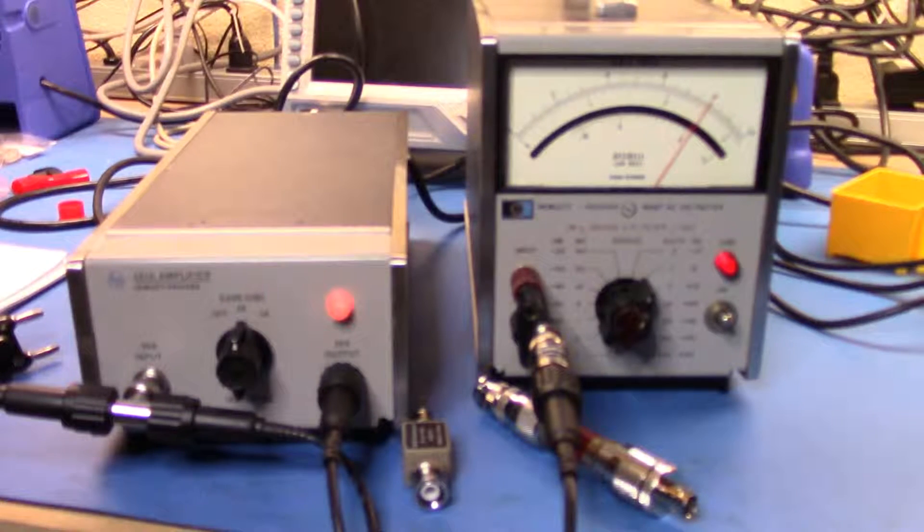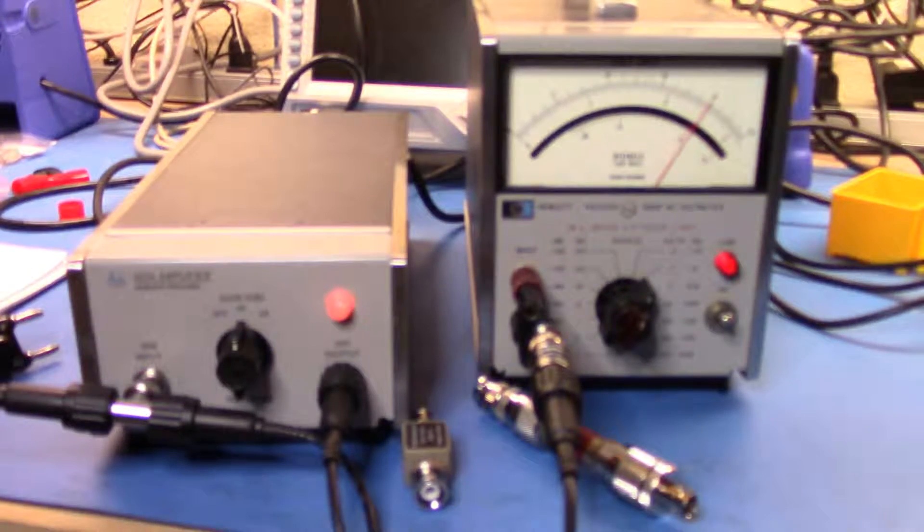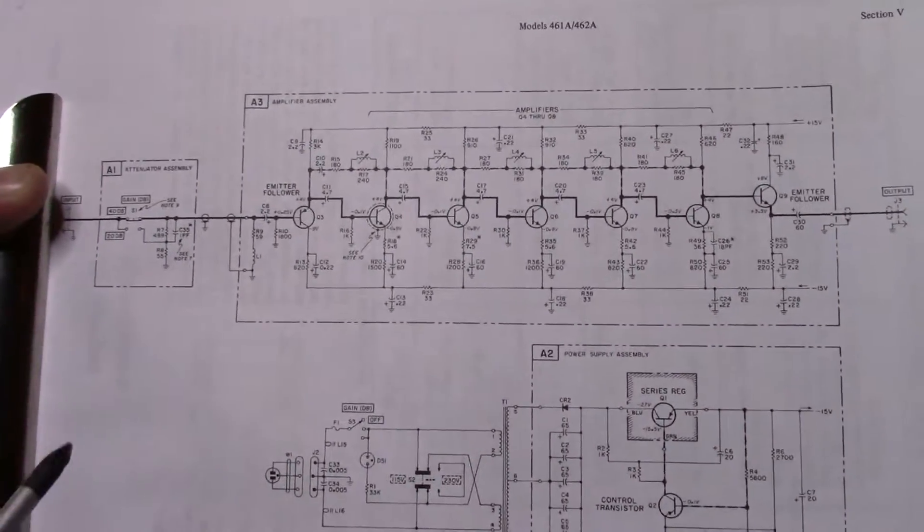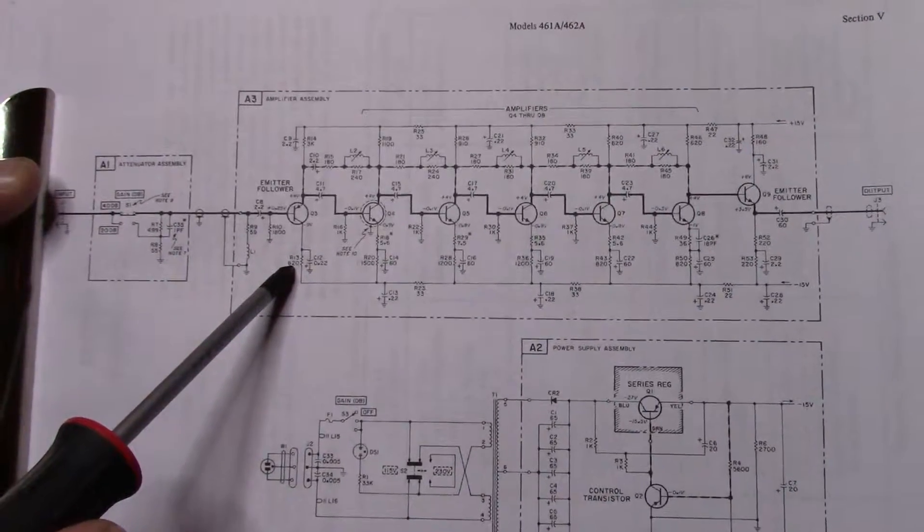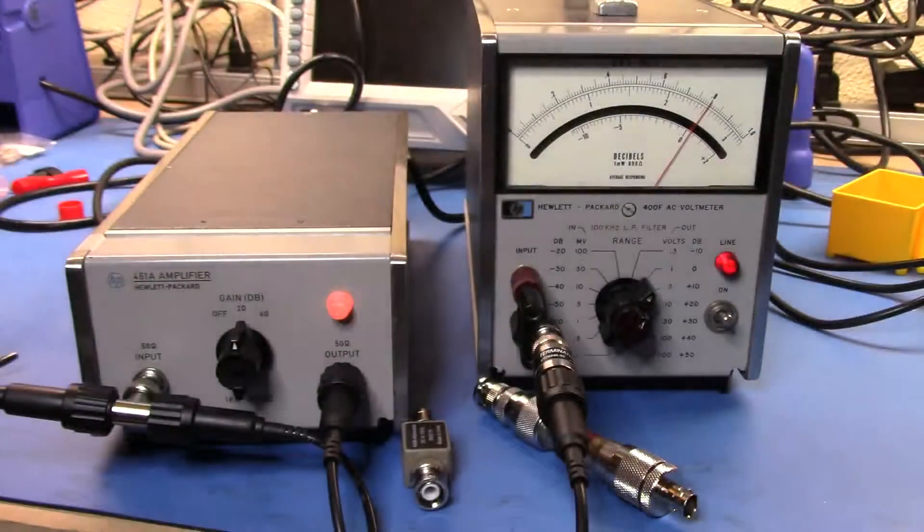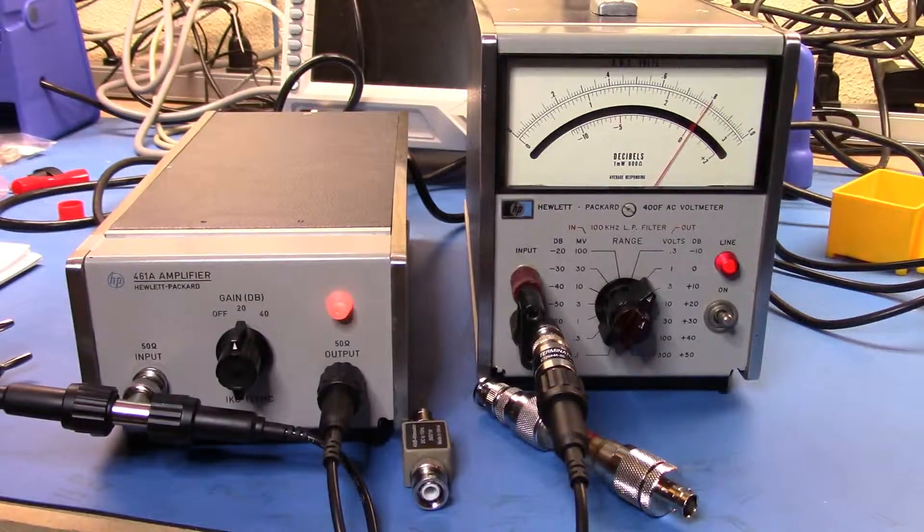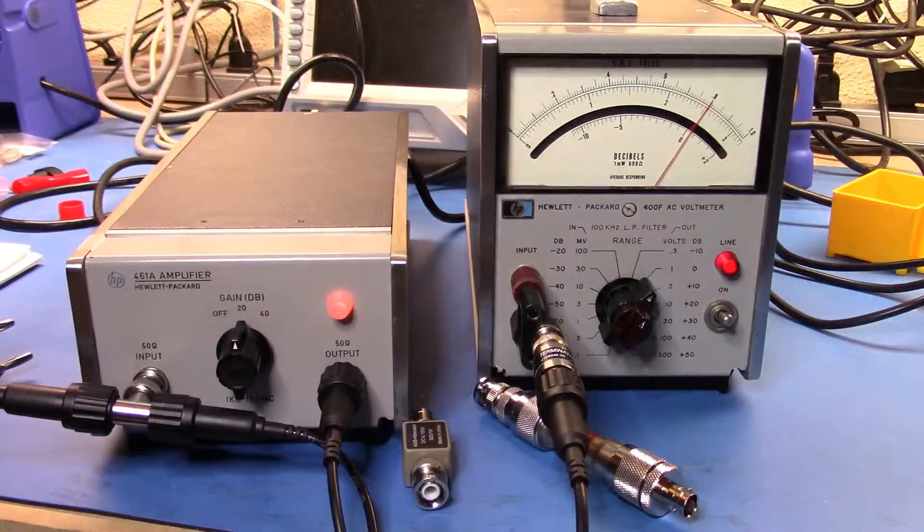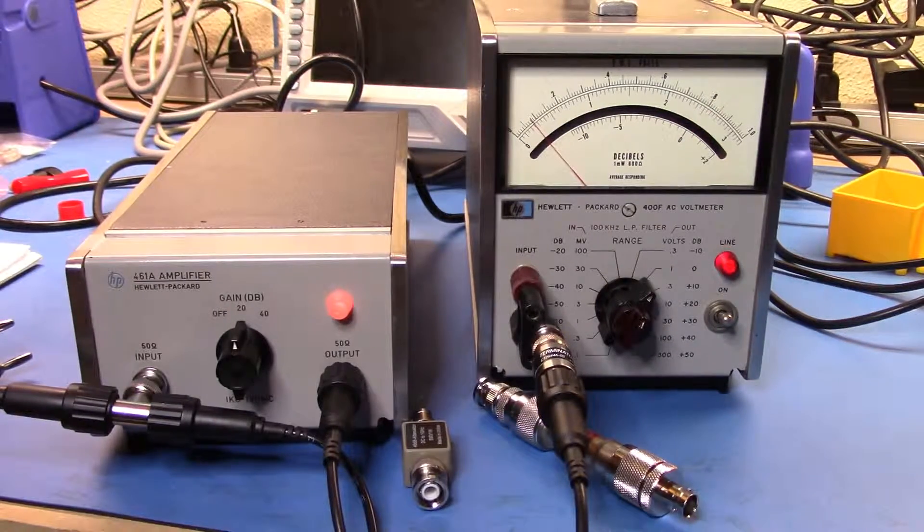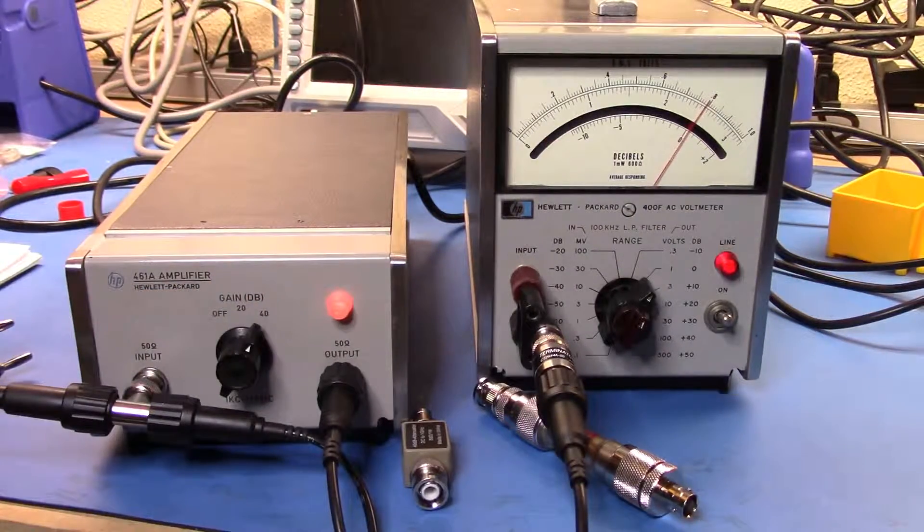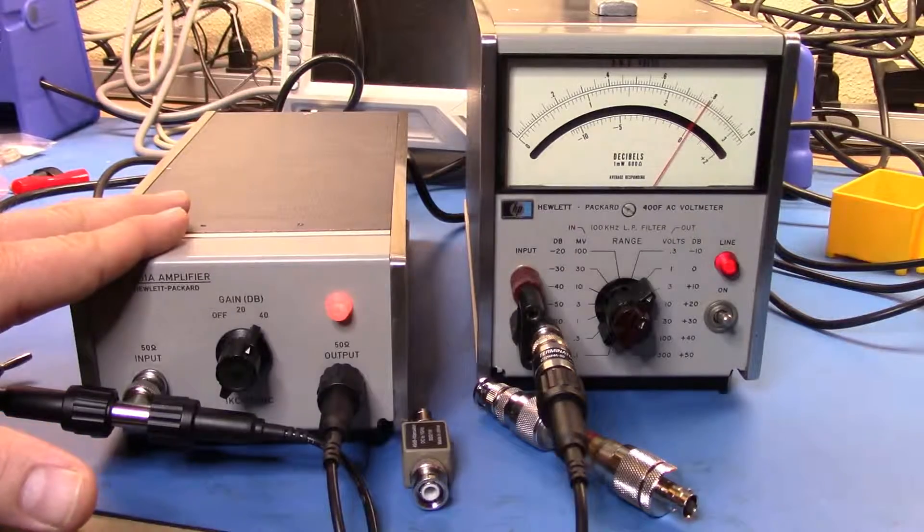Now the manual says you can calibrate the gain, and the way you calibrate the gain is by replacing a resistor. And in fact I think from memory the way you calibrate the gain is you're going to go in and replace R13 here, and that will enable you to tweak the initial gain on the entire amplifier. So I might go do that to restore it right back to its original gain. But you can see that I'm pulling in 0.8 there. So if I go in and change the amplitude of my signal generator to 10 millivolts and then set it to 40, you'll see that I'm roughly pulling in around the same 800 millivolts, and so that's now, I've now gone to 100 times gain on the 40 dB.